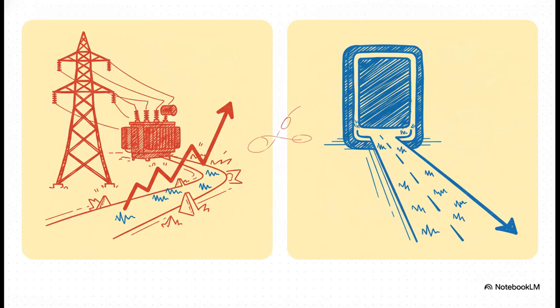On one hand, you've got the power grid itself, all those transformers and miles of lines. It has a natural inductance. Its opposition to current, its impedance, goes up as the frequency of that harmonic noise goes up. But capacitors do the exact opposite: their impedance goes down at higher frequencies. This basically turns them into a giant sponge, just soaking up all that harmonic noise.